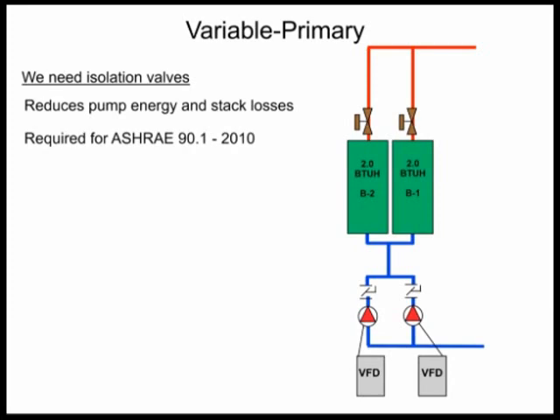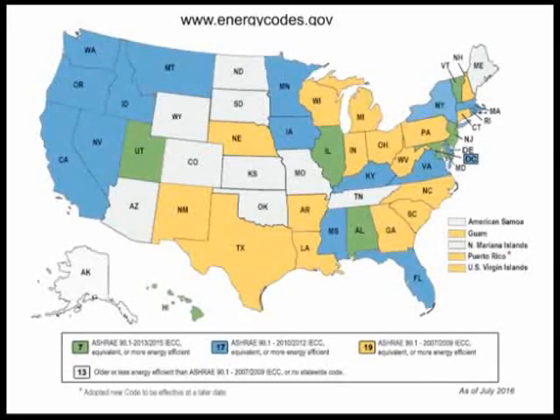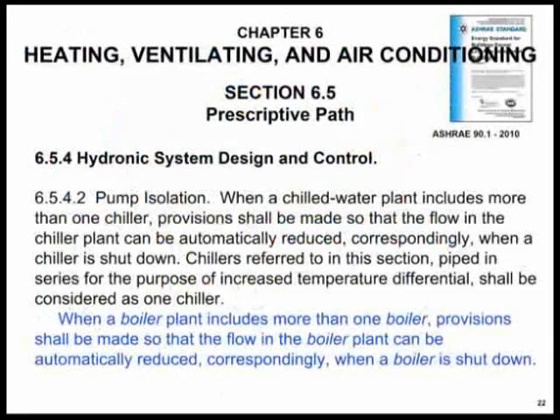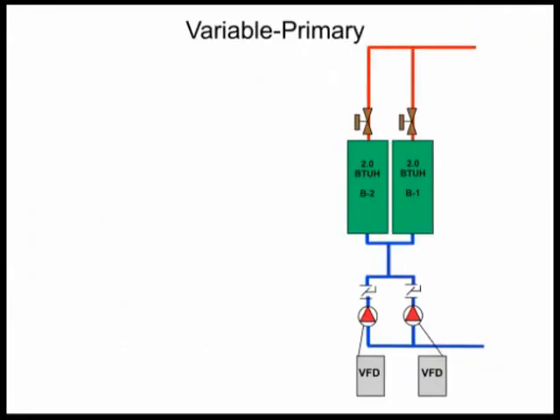What does your state stand for ASHRAE 90.1? You can look it up online. This map here is as of July 2016. You can see where your state is in terms of the energy code. ASHRAE 90.1 2010 addresses pump flow and boiler stack losses. Specifically, when a boiler plant includes more than one boiler, provisions shall be made so that flow of the boiler plant can be automatically reduced when a boiler is shut down — due to stack losses and pump energy. If you're not going to use the boiler, why would you pump water through it?